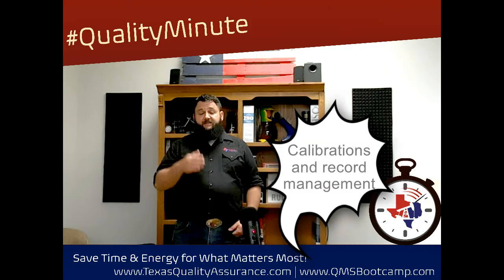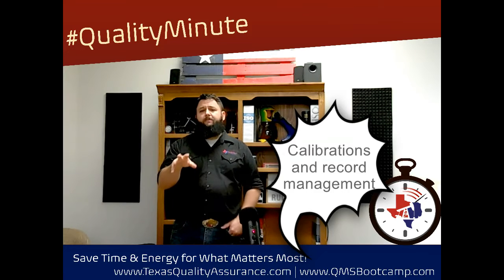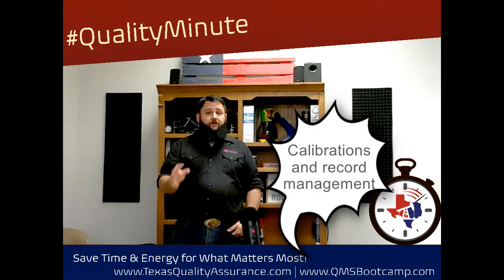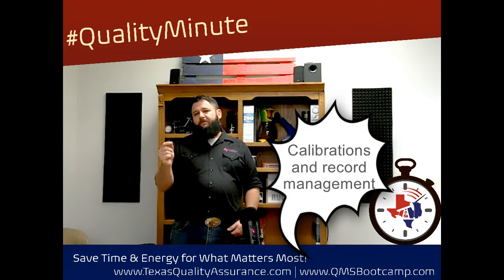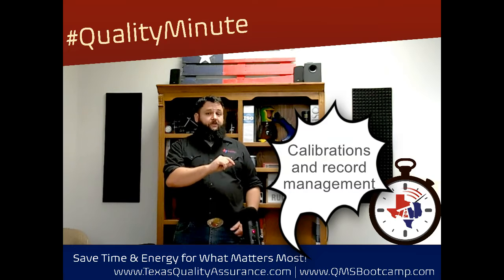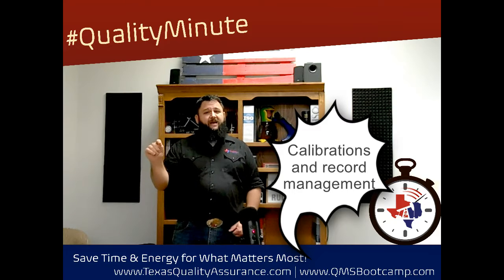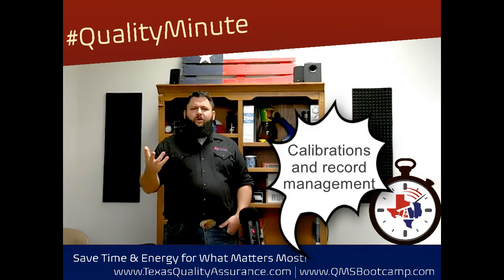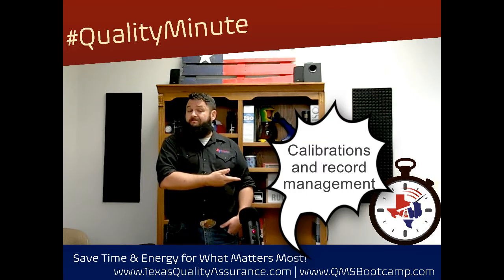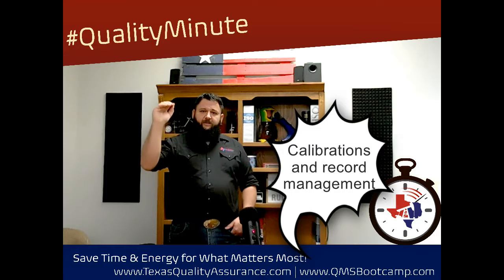But the typical process is that we get these tools inspected on an interval. Maybe they're checked on an annual or semi-annual, but we're going to check these tools on a regular basis to make sure they're still calibrated and good to use. The problem is if one of those tools was checked 11 months ago, it was good, and it's checked today and it's out of tolerance, it's bad, well, what do we do with all the parts that were checked with it in between?